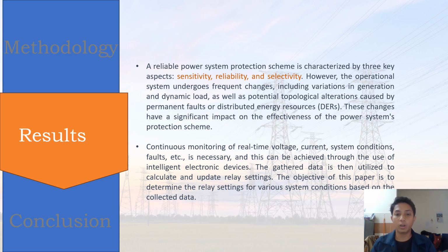Continuous monitoring of real-time voltage and current system conditions is necessary, and this can be achieved through the use of intelligent electronic devices. The gathered data is then utilized to calculate and update relay settings. The objective of this paper is to determine the relay settings for various system conditions based on the collected data.